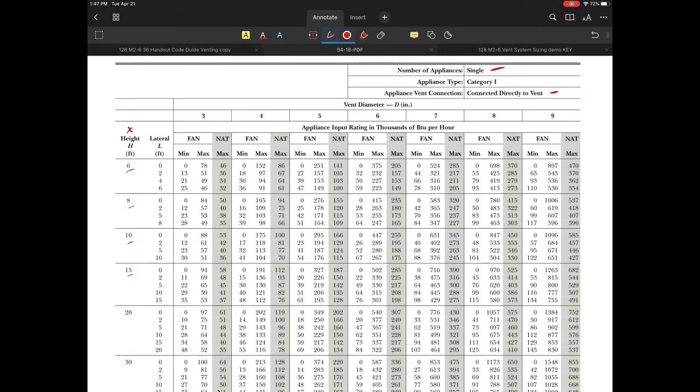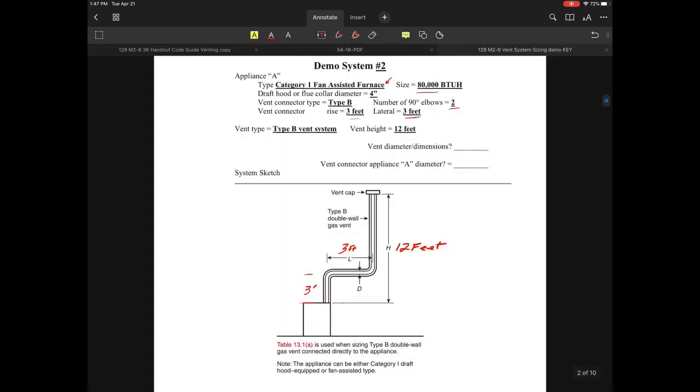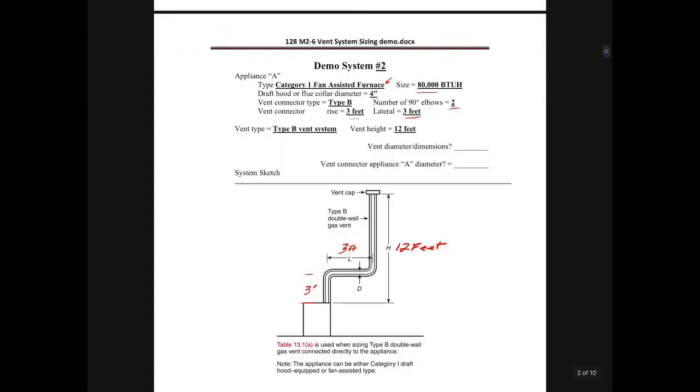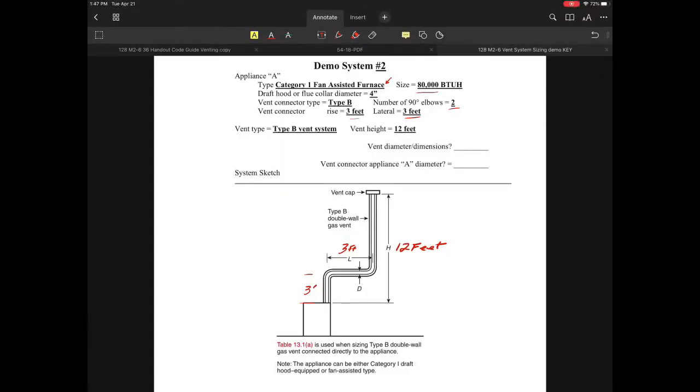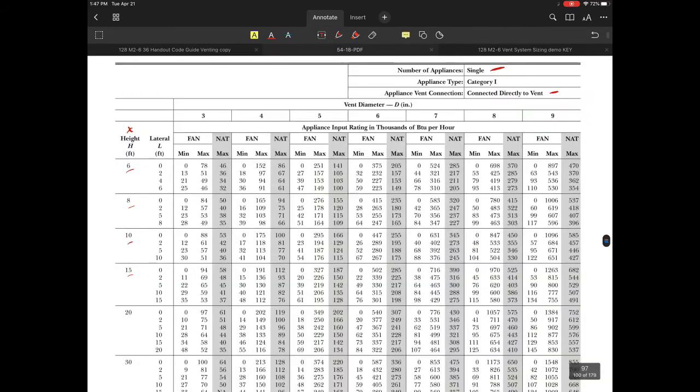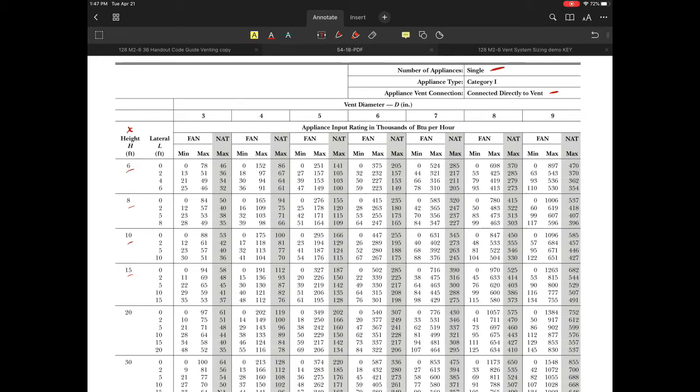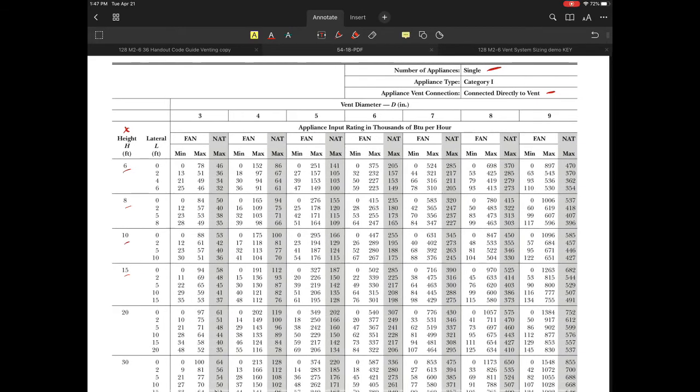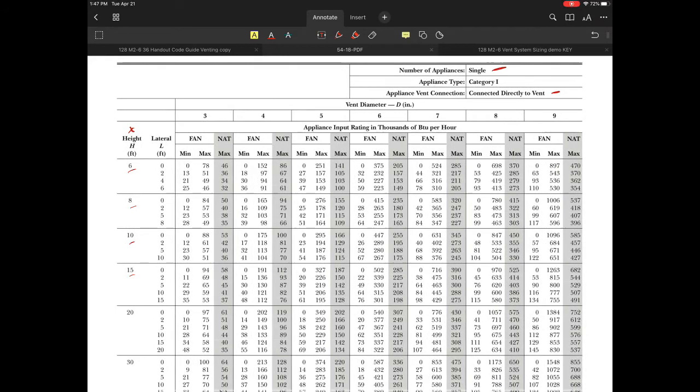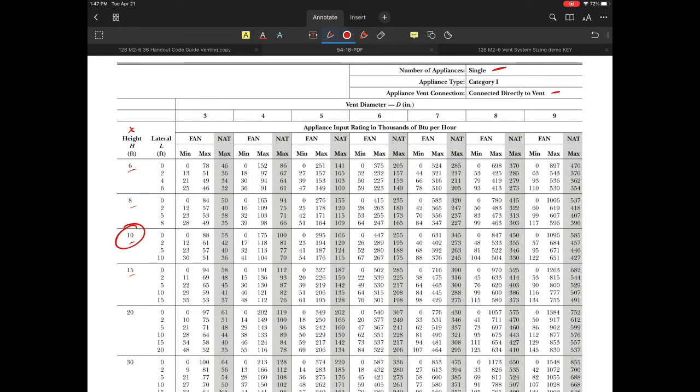The table gives vent heights of 6, 8, 10, and 15 feet. My system is 12 feet, which doesn't fit any particular table. I'll err on the side of a 10-foot high system and see if I can avoid interpolation. I'll use the 10-foot system values.